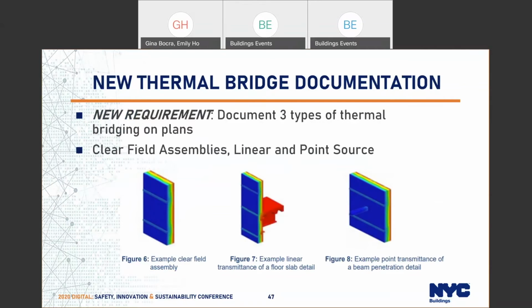There are three different types of thermal bridges that we want to be identified on the plans. First is the one that I've already mentioned, a clear field assembly. A clear field assembly is an area of a wall, for example, where we have a regular disruption of the insulation, like framing. Those have been taken into account in ASHRAE Appendix A. So those types of assemblies are usually already derated for the thermal bridge.